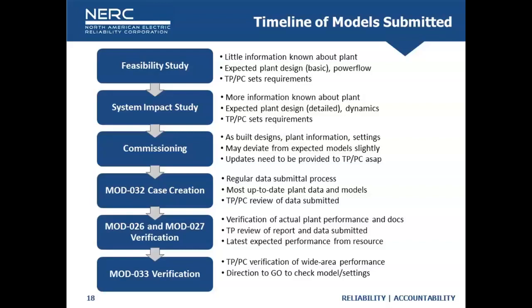Up until commissioning, that is an expected or planned design. When you get to the actual commissioning test, you then have as-built designs - actual plant information, impedance values, control settings, power plant controller settings, inverter settings, etc. These may deviate from the models provided during the study process, and those updates, once the plant goes into commission, need to be provided to the TP and PC as soon as possible per the standards.